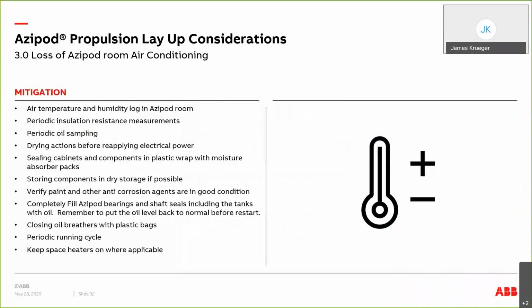And again, the mitigation would be to keep the AC system running, keep a temperature and humidity log, and make sure that it's not getting out of control. We do recommend still to do the periodic oil sampling. And there may be a need to do some kind of drying actions on certain equipment prior to reapplying the electrical power when the time is right. So in the case where humidity levels were high, typically insulation resistance will go down. And if it gets to a critical point, then of course it's not recommended to re-energize until we can get that insulation resistance back to an acceptable level.